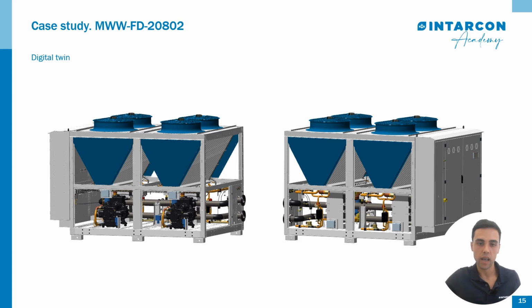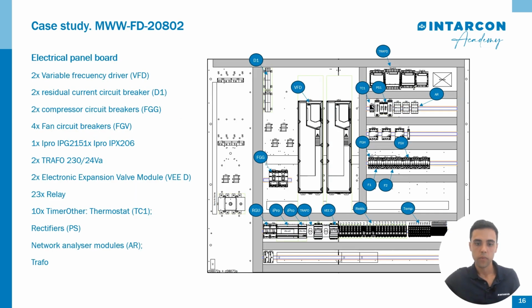We can see in this slide the digital twin of this equipment, which is a key factor for the design department, where we use the CAM and CAE design process to anticipate failures and improve our system very quickly. And now we see here the electronic panel board with the different elements and components, such as the variable frequency drive, the circuit breakers for compressor and fans, the use of the iPro control programmer, the electronic expansion valve modules, and other elements and components that we see in the next video.